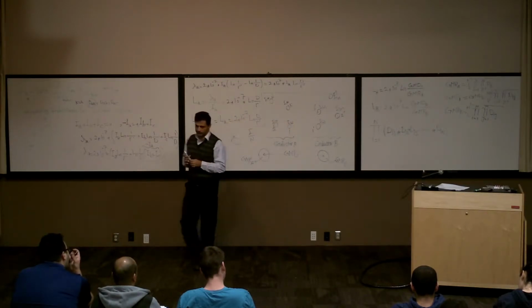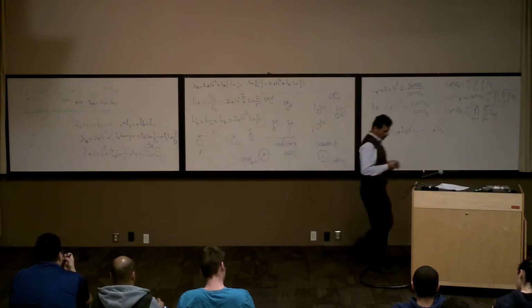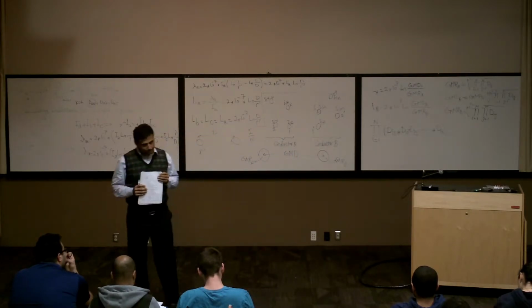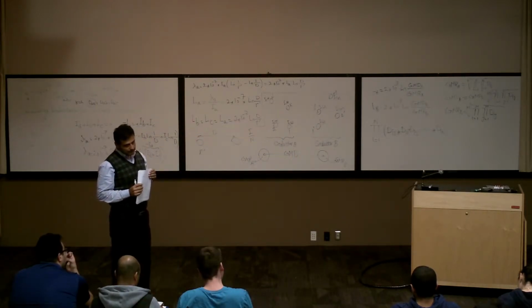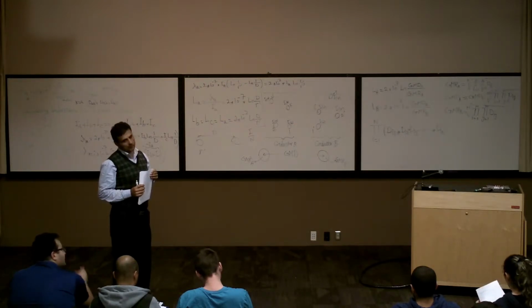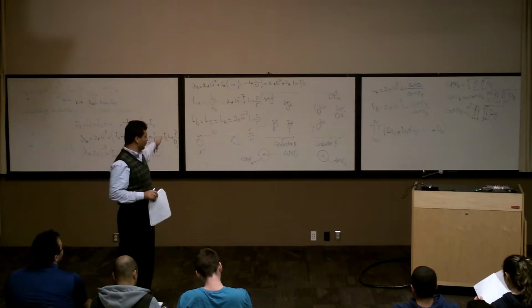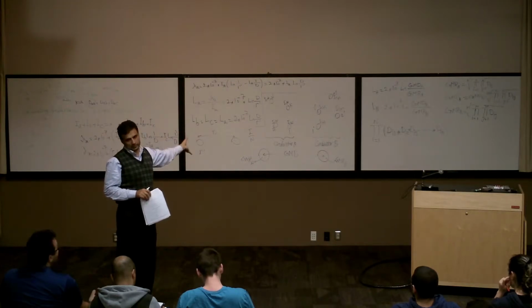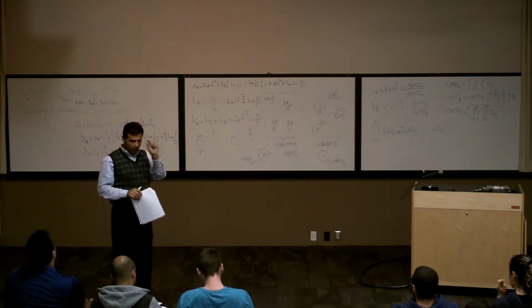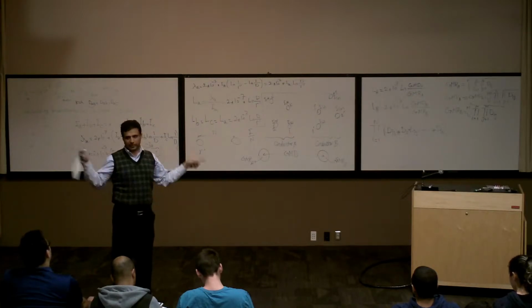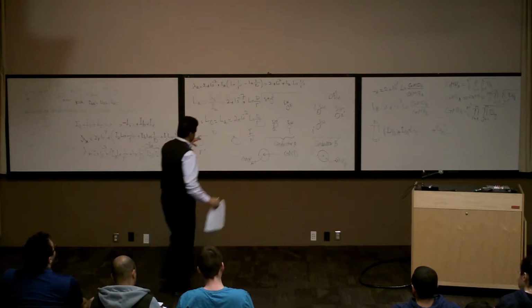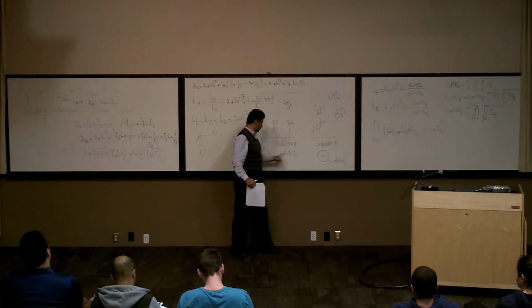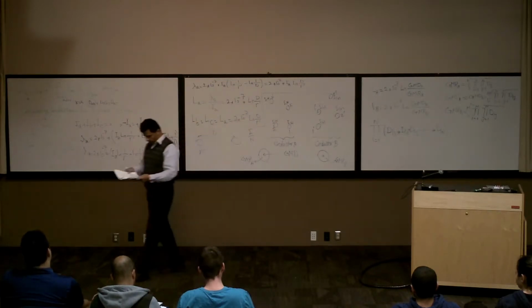Now let's go to one example here to explain this a little bit better. So these GMRA, GMRB, GMD, we're just modeling each of these blocks as just one conductor. As I said, we're modeling the multi-string conductor with one string. We know if it's one string, we need an R prime and we need a D, right? But how to replace this one with one equivalent? R prime should be this much, and the D should be this much. We're calculating. Let's go through this example from the book.